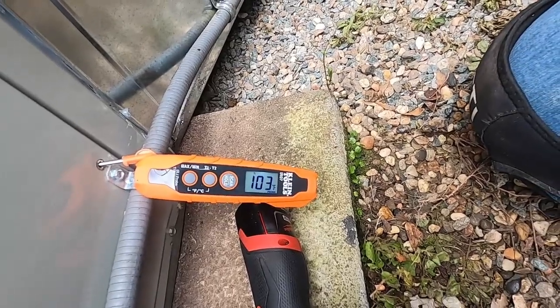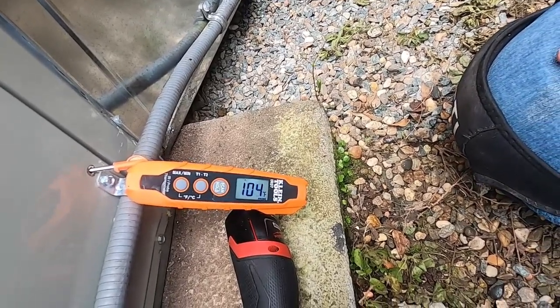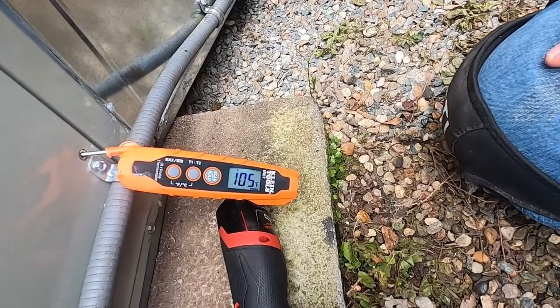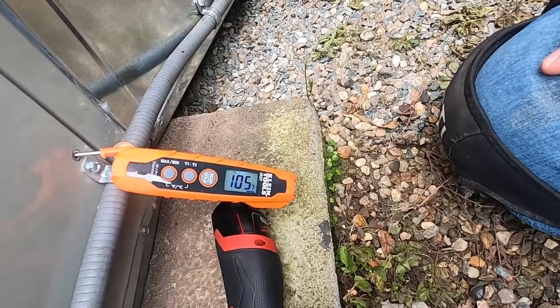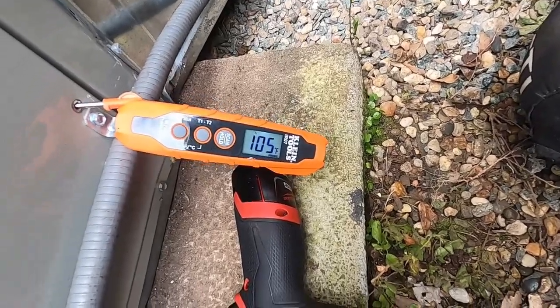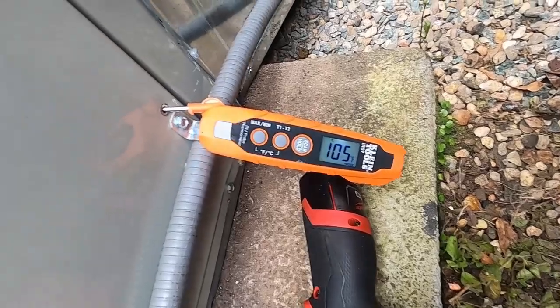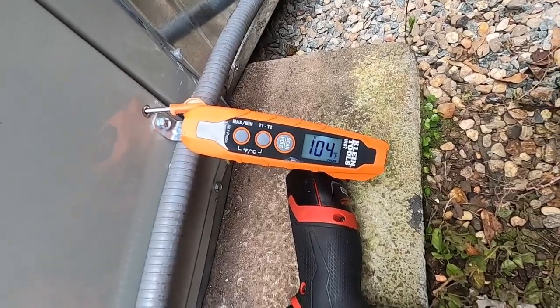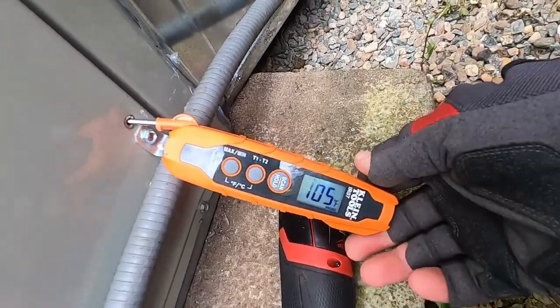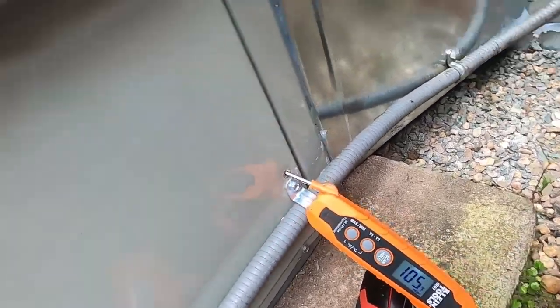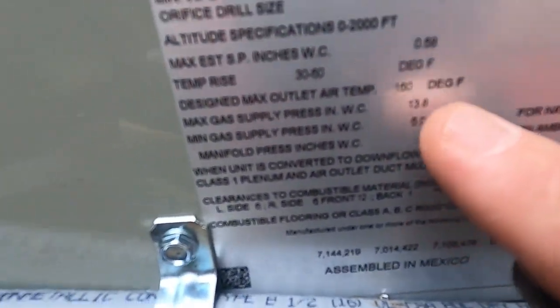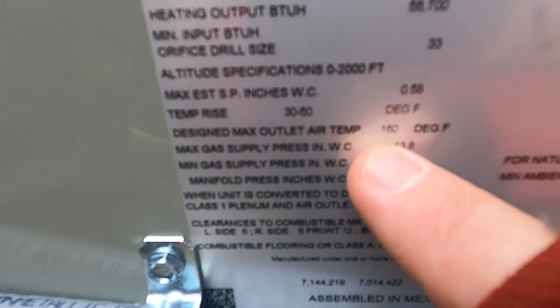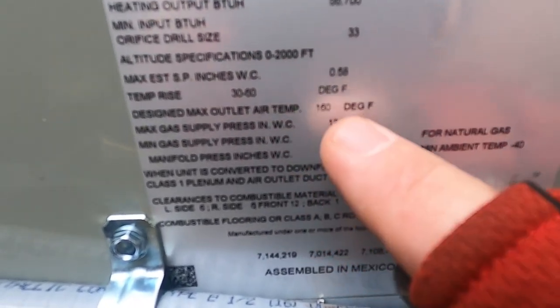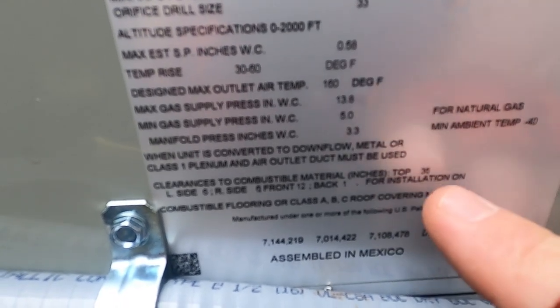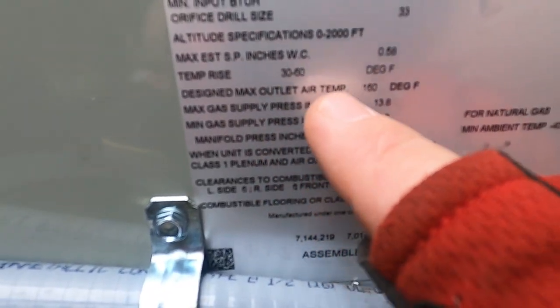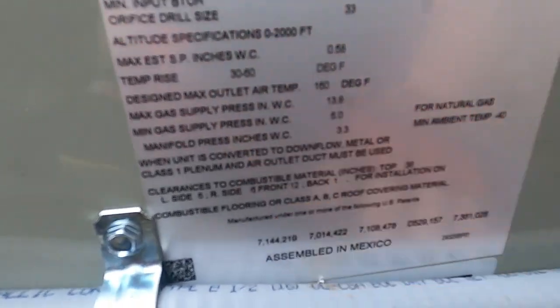And this is a 70,000 input, 56,000 output. About a 40-degree rise. So the design max outlet is 160. And they put your rise on this thing at 30 to 60 degree rise right there.